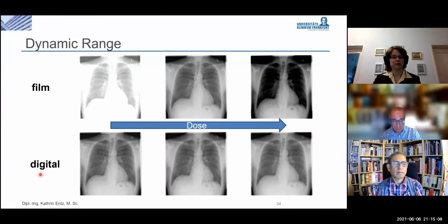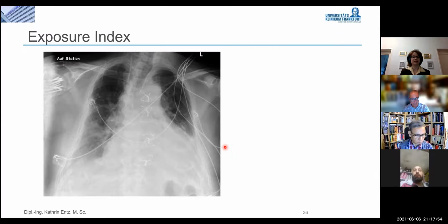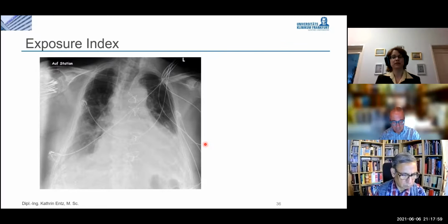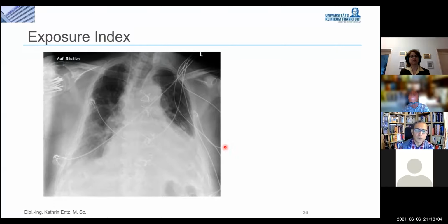And here we have an example of one of our mobile units that is used in the intensive care unit. It's a new system that we bought last year. So during the Corona pandemic, it was not possible for the specialist from our vendor to accompany the radiographers to the intensive care unit and to configure the system properly. So unfortunately, we had to work with standard parameters, and that resulted in an image like this. So maybe you can see that it's not ideal, that the image quality is not perfect.